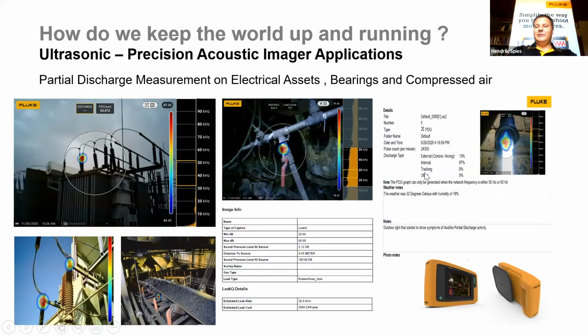Is it internal? Is it tracking? Or is it another type of partial discharge? If we look at the actual application for mechanical, we can pick up bearings that are starting to fail, because they will start to emit ultrasonic sound. And typically this is problems with lubrication or aging of the bearing.